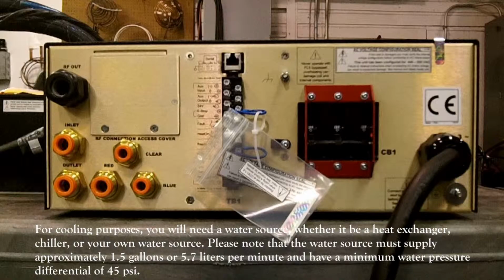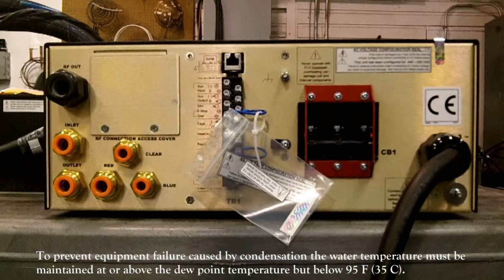For cooling purposes, you will need a water source, whether it be a heat exchanger, chiller, or your own water source. Please note that the water source used with this EASYHEAT Li must supply approximately 1.5 gallons or 5.7 liters per minute and have a minimum water pressure differential of 45 psi, ideally between 45 and 80 psi. To prevent equipment failure caused by condensation, the water temperature must be maintained at or above the dew point temperature, but below 95 Fahrenheit or 35 Celsius.